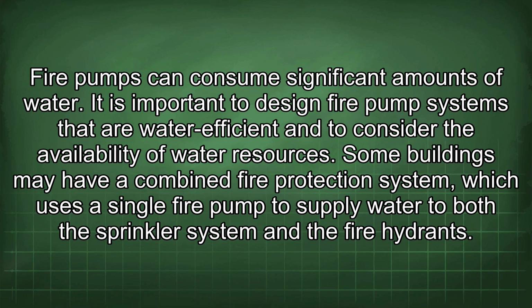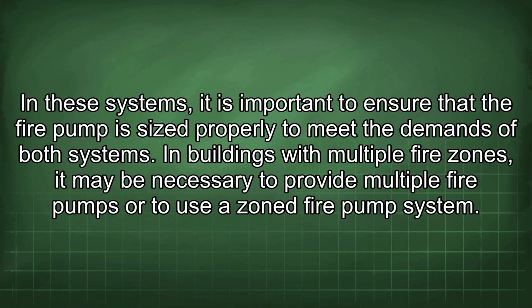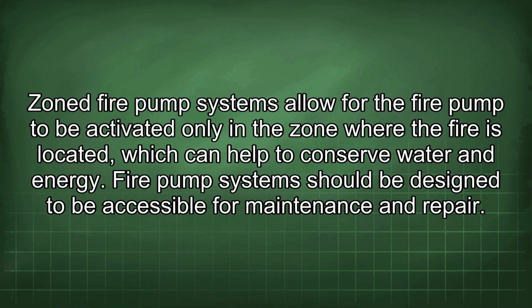Some buildings may have a combined fire protection system, which uses a single fire pump to supply water to both the sprinkler system and the fire hydrants. In these systems, it is important to ensure that the fire pump is sized properly to meet the demands of both systems. In buildings with multiple fire zones, it may be necessary to provide multiple fire pumps or to use a zoned fire pump system. Zoned fire pump systems allow for the fire pump to be activated only in the zone where the fire is located, which can help to conserve water and energy.